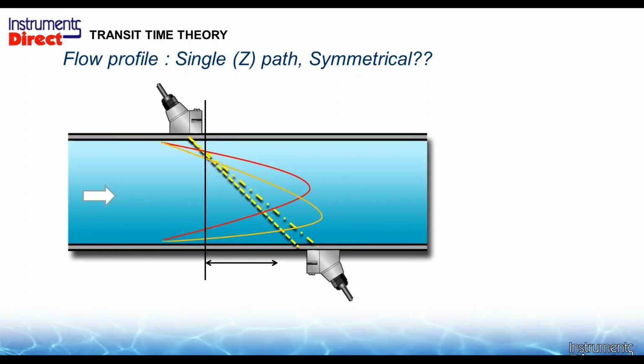Now, the trade-off here, rule of thumb, is you install it the way you're supposed to. Mathematically, you'll have the optimum accuracy of your flow meter. When I begin to profile the transducer to find the sweet spot, I'm now less accurate than the optimum position. How much inaccuracy? Can't answer that. It's a function of what's causing the situation. It could be a lack of straight run of pipe. It could be a chunk of something inside the pipe. You could have put the math in wrong on the pipe. The pipe may not be perfectly round.